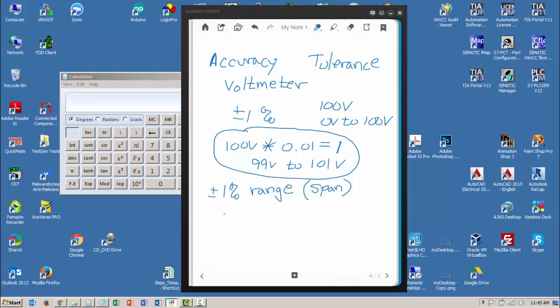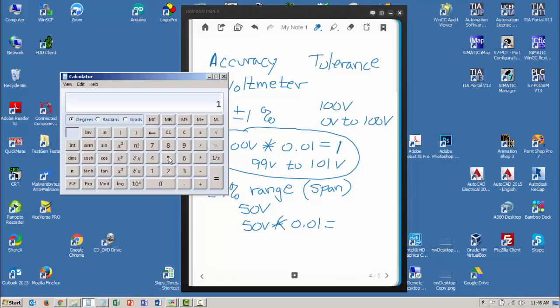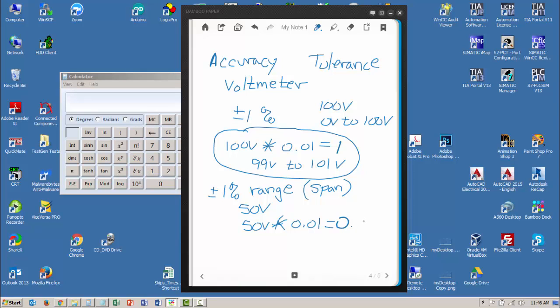If I'm reading 50 volts, let's say I'm reading 50 volts. Now let's calculate the tolerance at 50V. So 50 volts times 0.01 is equal to—and we'll use the calculator—50 times 0.01 equals 0.5. So my solution here is 0.5.